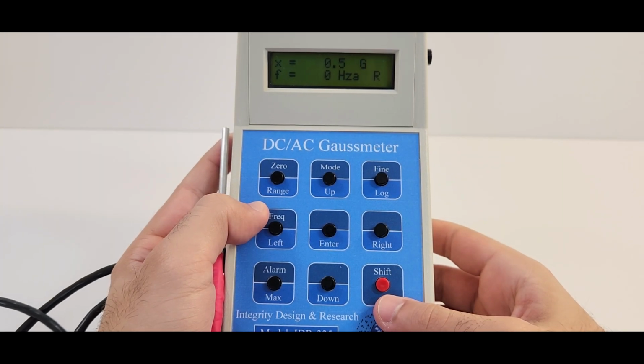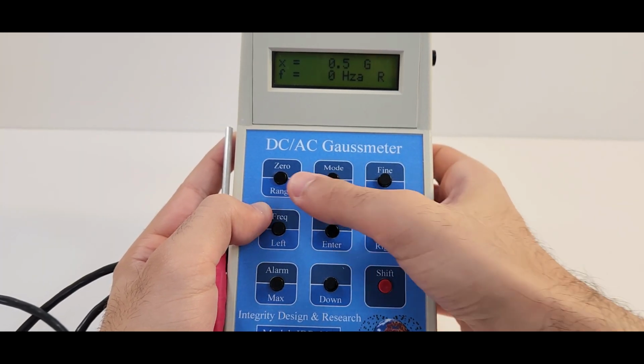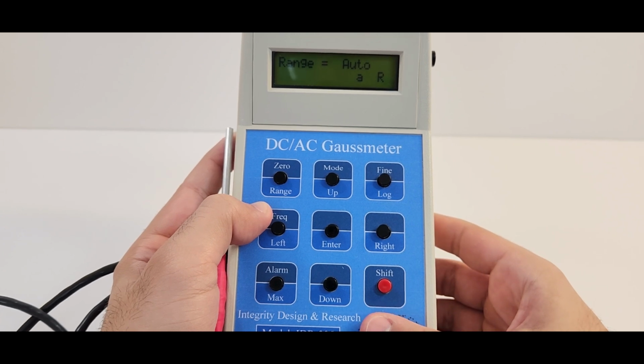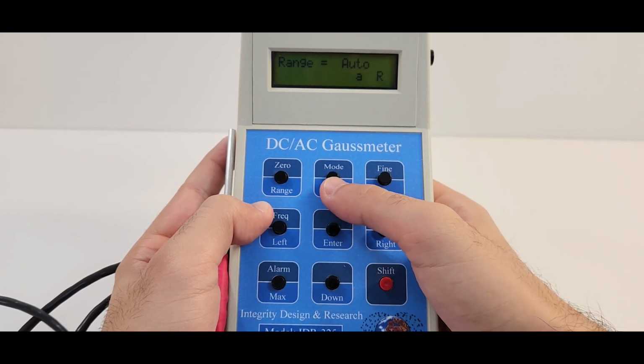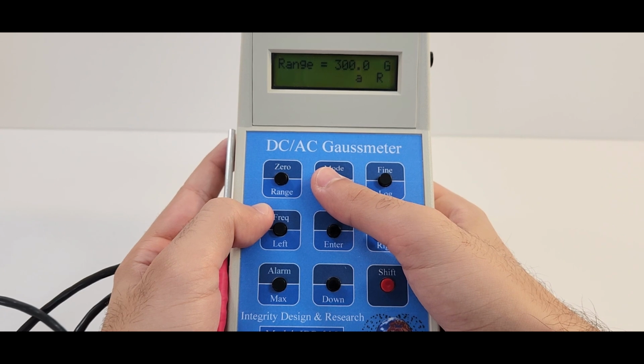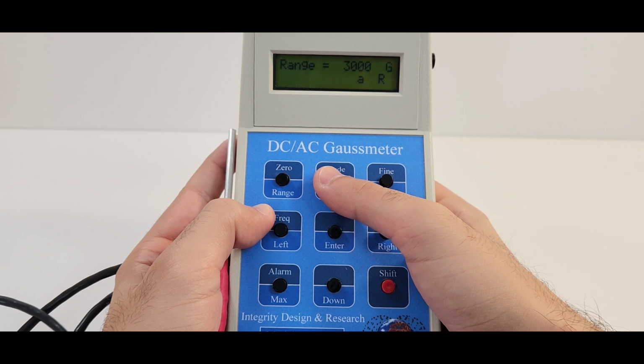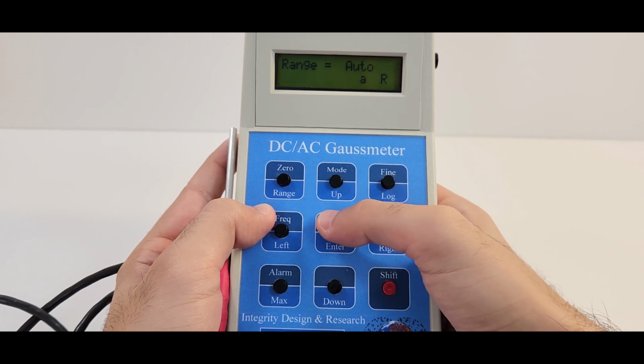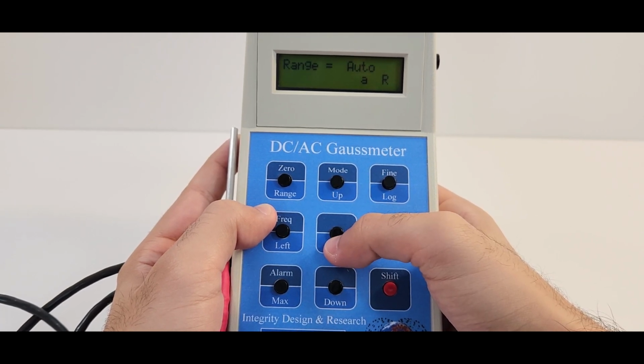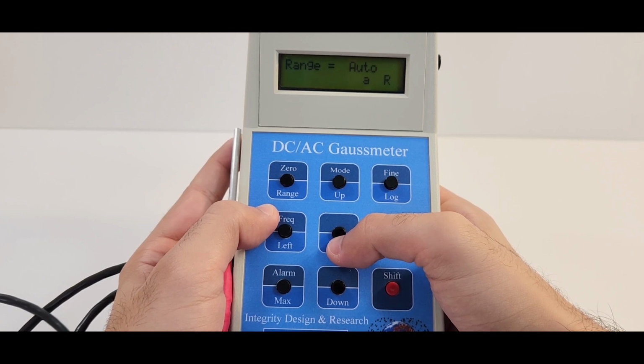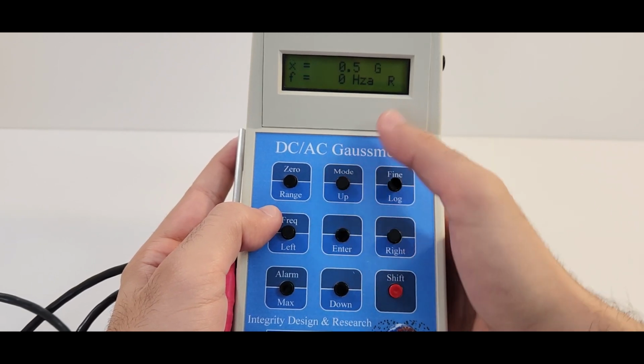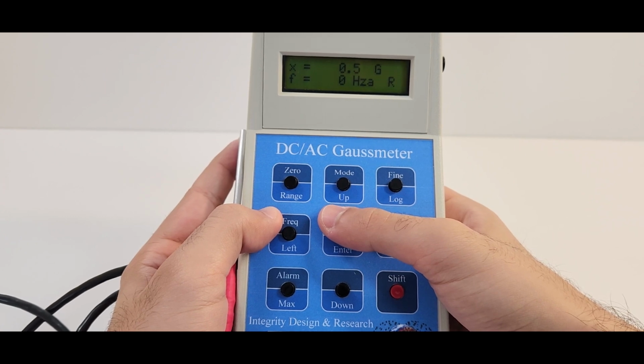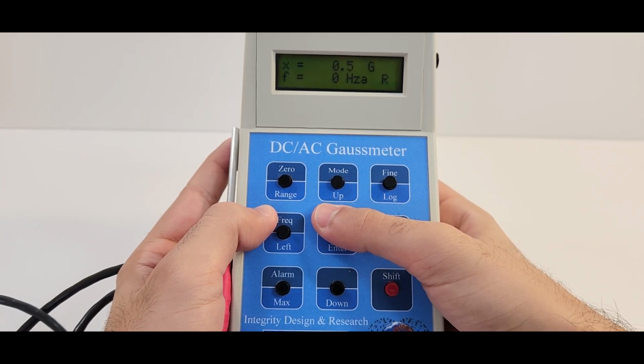To change the range of the device, press the Range button. By default, it's in Auto mode. You can cycle through the options by pressing up or down, starting from 300 Gauss, 3000 Gauss, and lastly 30,000 Gauss, in other words 30 kilogauss. However, for basic applications, you can use the Auto mode, but it's recommended to use one of the three specified ranges. The designator R will be continuously displayed in the bottom right corner while Auto mode is on.